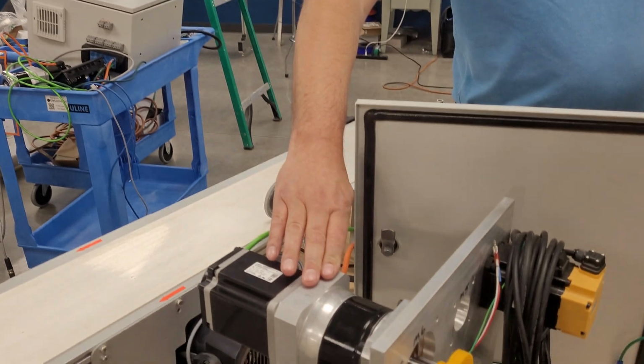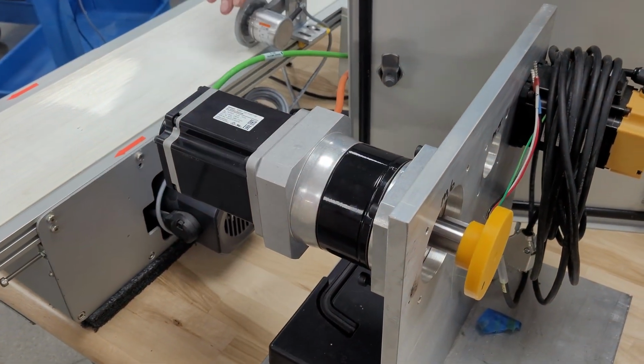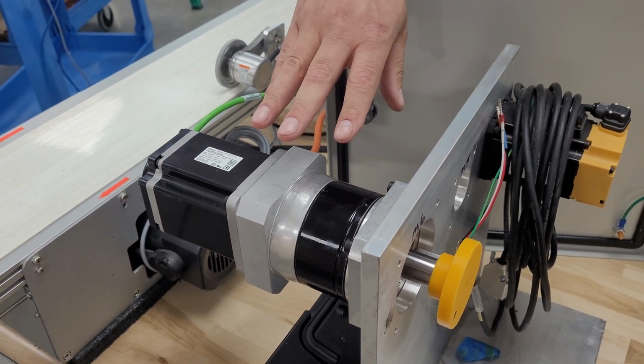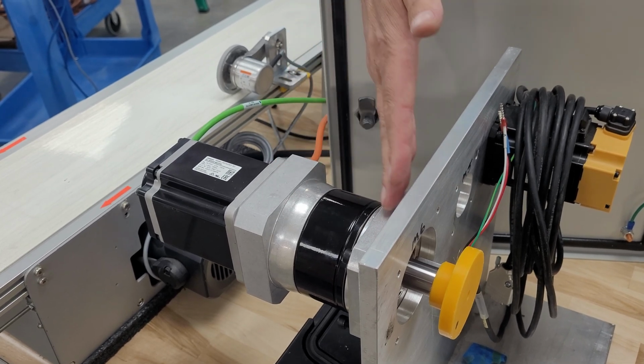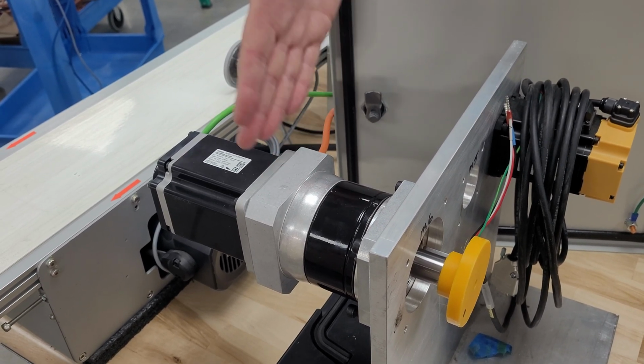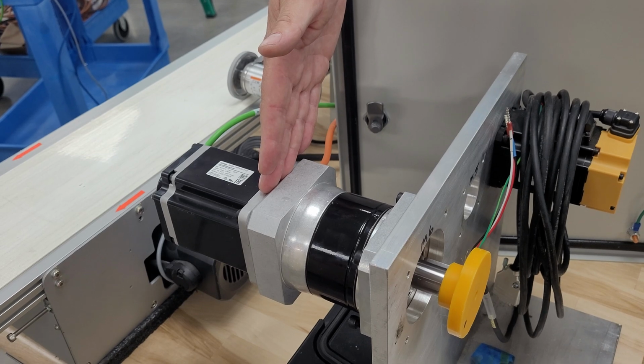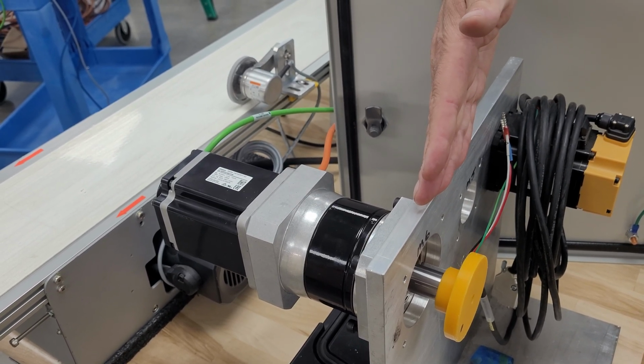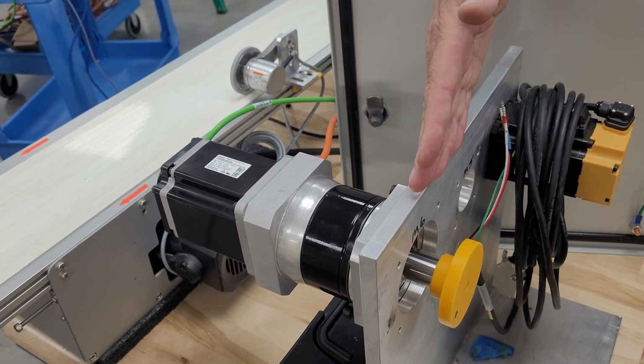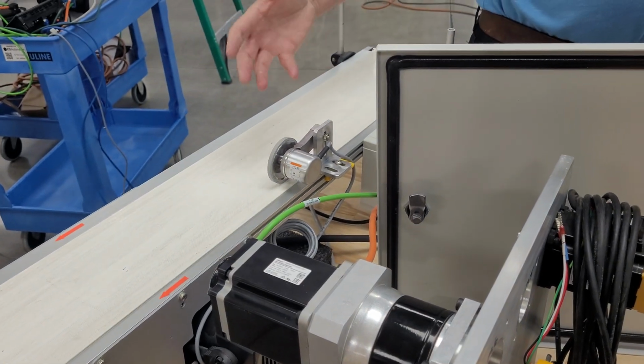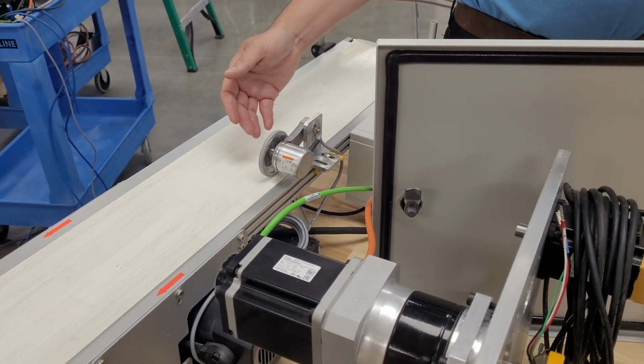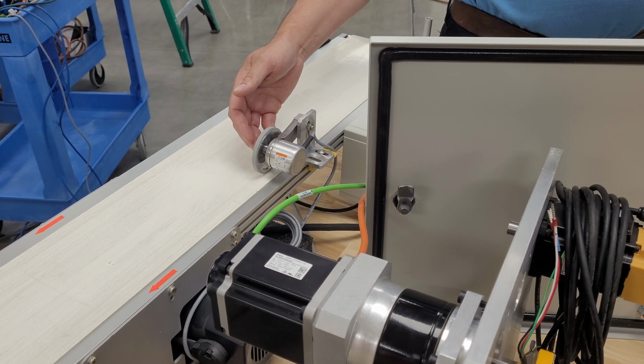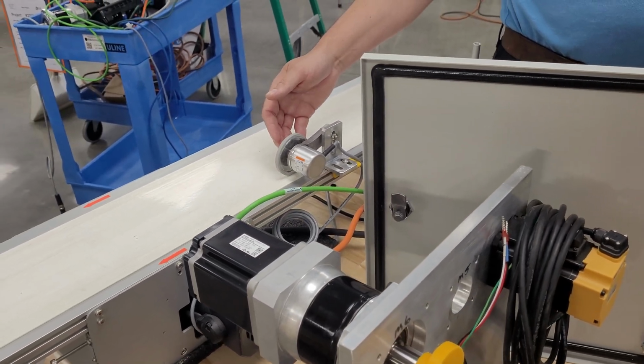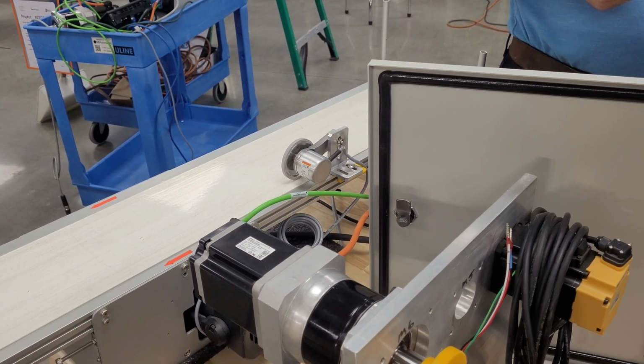Just like a mechanical gear, as you see it here, an electronic gear follows its source. The mechanical gear has a fixed ratio, in this case 10 to 1, so 10 revolutions on the ingoing side result in one revolution on the outgoing side. With an electronic gear, that ratio is fully variable. So we can adjust the ratio on the fly to follow a source, changing the output revolutions.